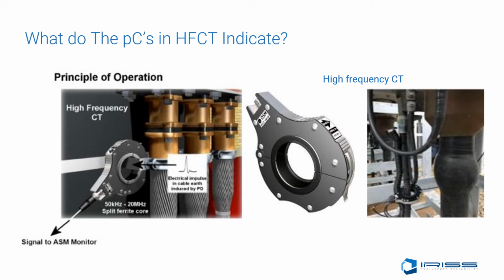As the insulation breakdown worsens, the burst interval will shorten due to the breakdown happening at lower voltages. This burst interval will continue to shorten until a critical 2 millisecond point is reached. At this 2 millisecond point, the discharge is very close to the zero crossing and will fail with a full-blown discharge and major failure. The HFCT mode needs to be used since there is only a small magnitude and short duration of these PD events.